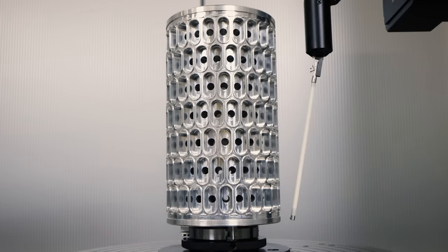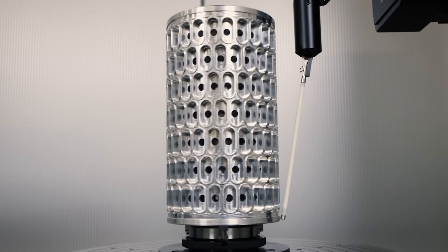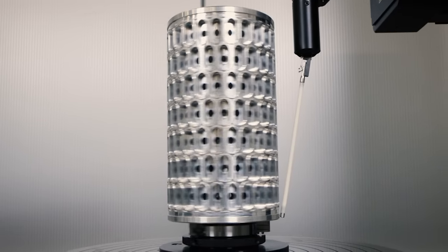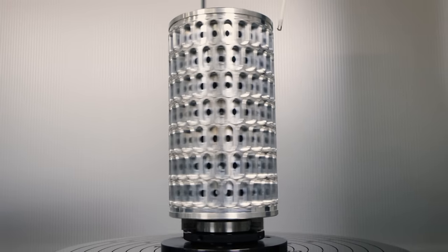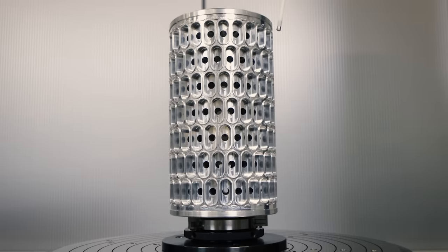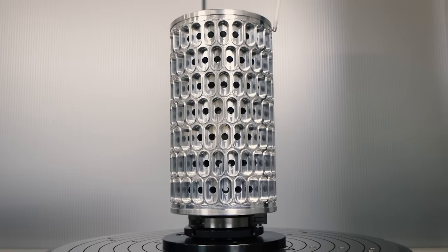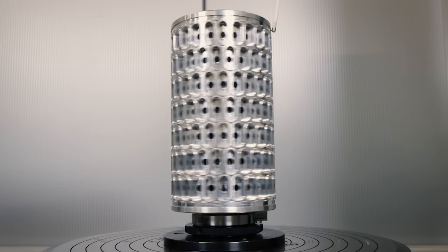To ensure you can work as accurately as possible, the workpiece must be aligned at the start of each measurement by the Round Tracer's fully automatic and motorized centering and leveling function. For this we are creating a workpiece axis by measuring, for example, two rotational profiles.